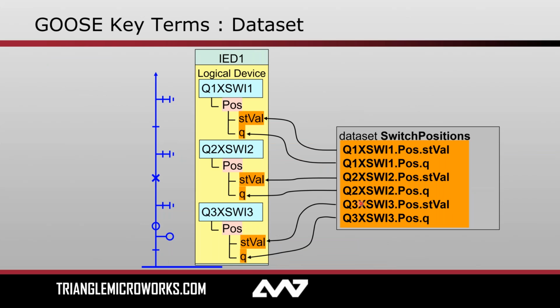So key term alert. Just like we had data sets for the world of client server communications, we also have them in GOOSE. There is one key difference, and that's really what I would like to point out on this slide. And that is that with GOOSE, we typically do not include an entire data object, but instead individual data attributes. So you might be thinking, what's the difference? If I have a position and I had a functional constraint of ST, what would be missing? Well, the answer in this example anyway is the time attribute. Because GOOSE is so fast, we're talking on the order of single-digit milliseconds, the time attribute is just not important, and it's seen as extra overhead to include it on the wire. So if I am notified within 3 milliseconds of a change, then do I really need to include the timestamp in the data set? That's the general thought.